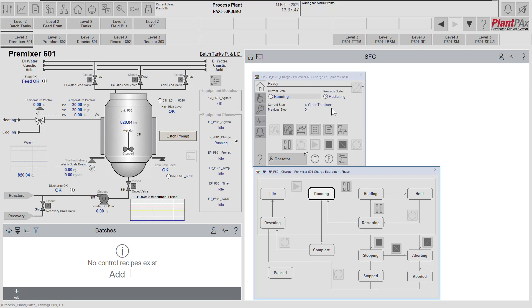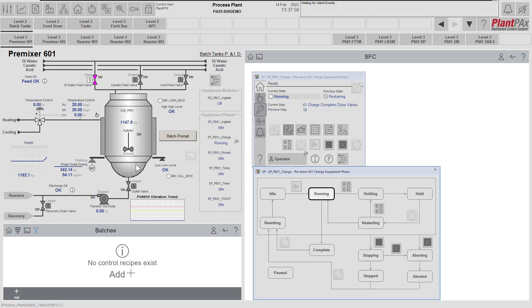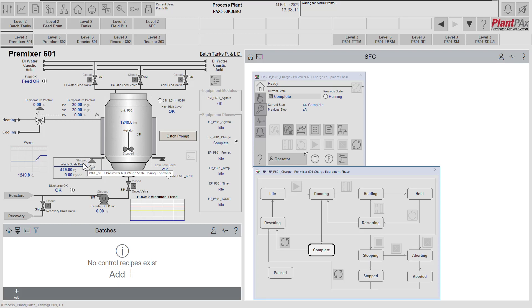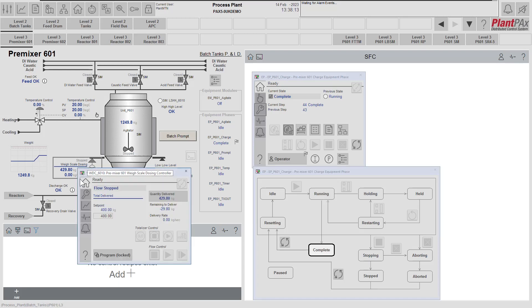We can see now that it's clearing its totalizer, starting the totalizer, and it's now opening the DI water valve and performing that charge on the vessel — the weight is now increasing. The charge has now successfully completed and the weight has gone up. You can see the dosing controller was used and has completed the dosing it was asked to do: the 400 kilograms that we requested.